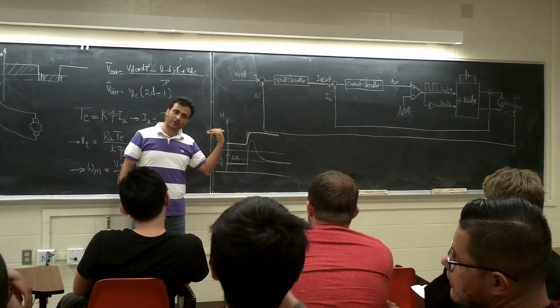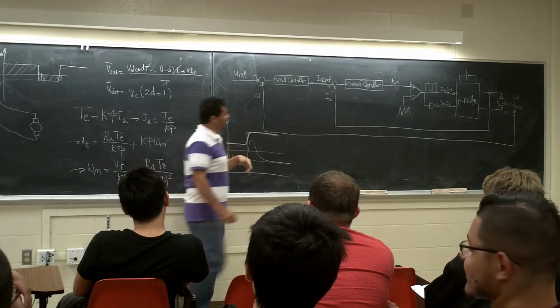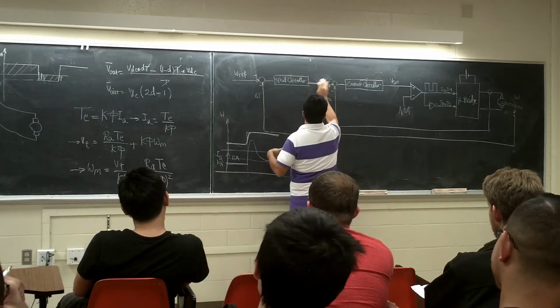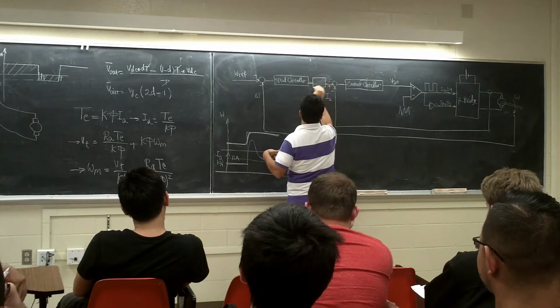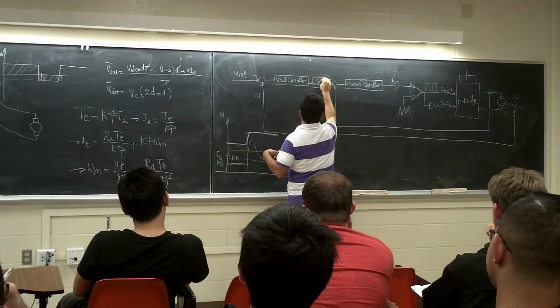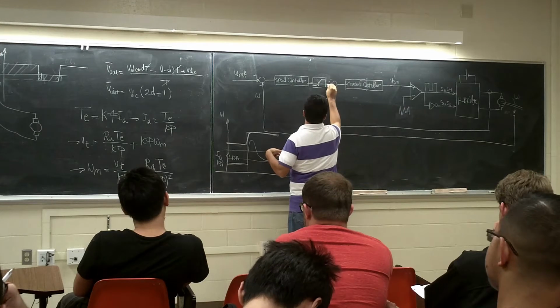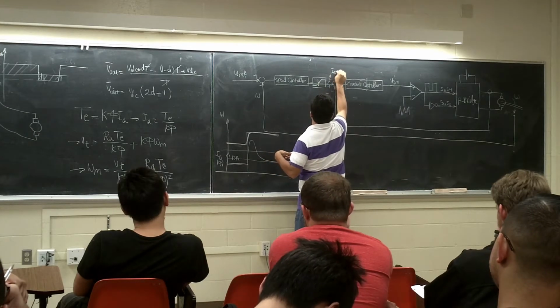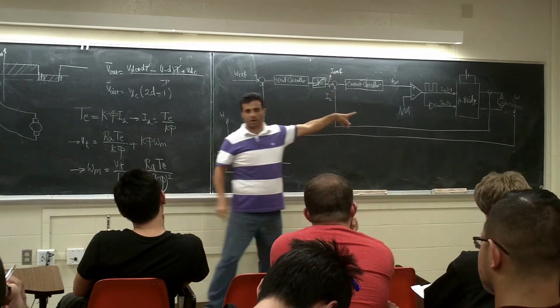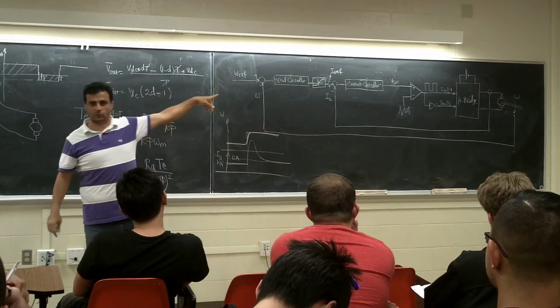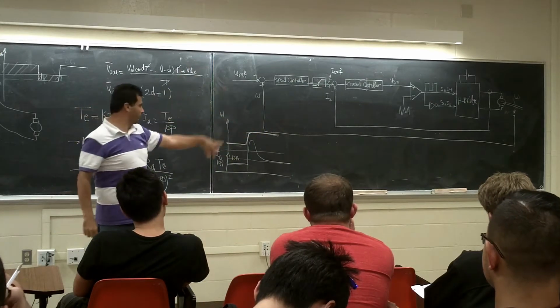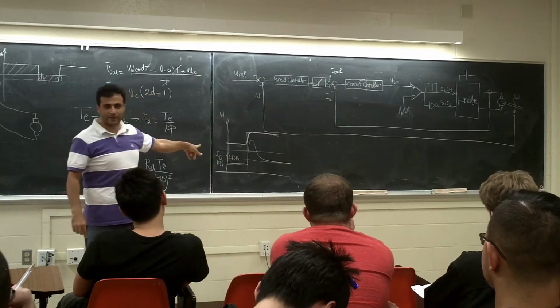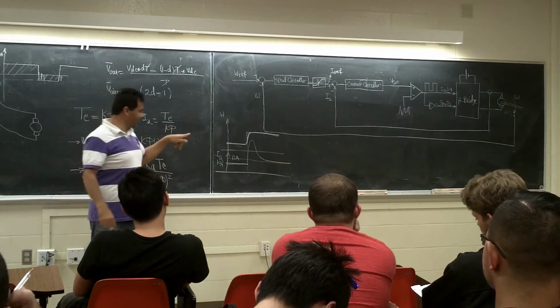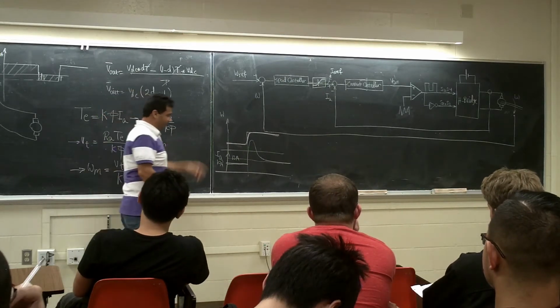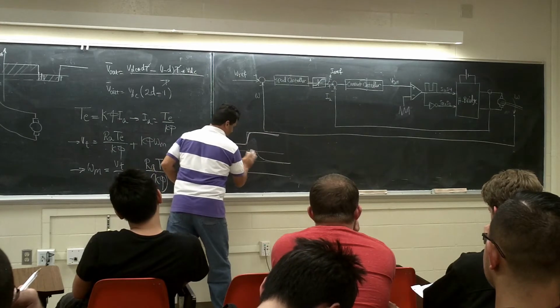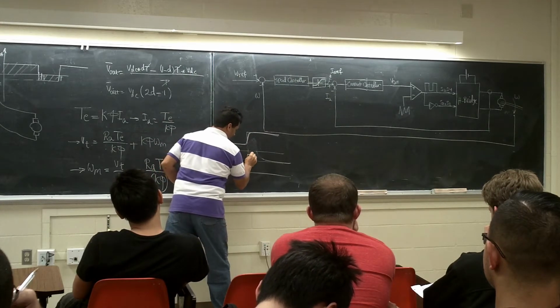Now what does the internal current loop do? Usually there is a limiter here, and this is the IA there. I know how much is my limit, how much I can send to this system. I can handle, for example, only 20 amps in this case. What happens when I have that? It's not going to go past that, you're going to go to 20 amps.